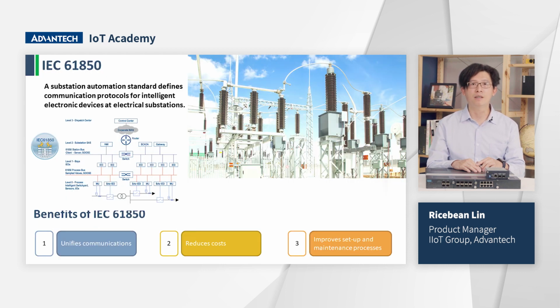IEC 61850 is a substation automation standard that defines the communication protocol between different equipment such as protection, control, and measurement equipment, as well as the IED. Why did the IEC 61850 become so successful? There are three benefits. The first one, unified communication, avoids the proprietary protocol. The second, reduced cost, for example, wiring and engineering times. The third, improved setup and maintenance process.